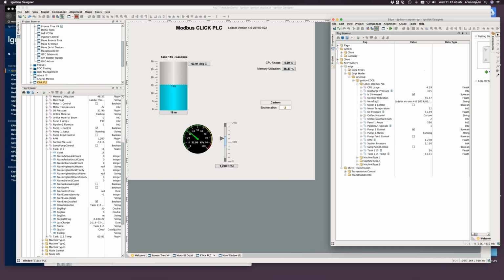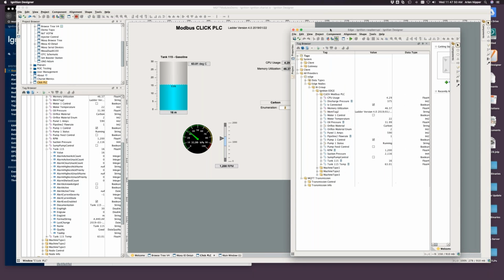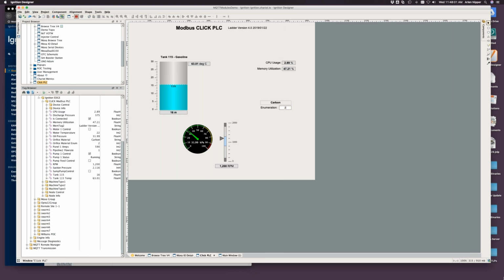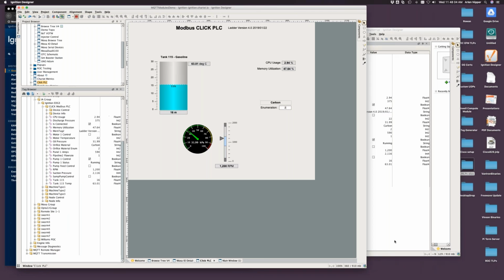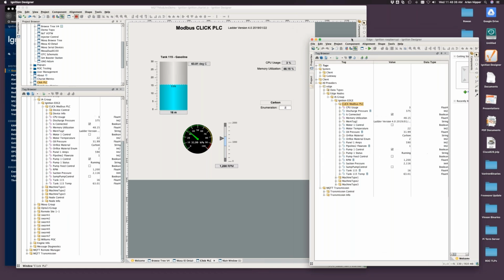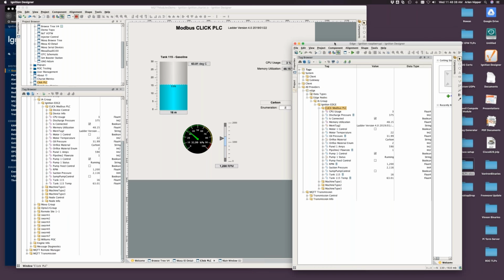This is the console for Ignition Edge. Now, this is running on a Raspberry Pi. And if you'll note, my tag structure is identical on the edge to what it is over here in my Ignition Gateway. So what I was able to discover in just a few seconds and publish was all recognized by the Ignition Gateway, and I can immediately start using those tags. Now let's take a look at that. Let's go into that tank 115.